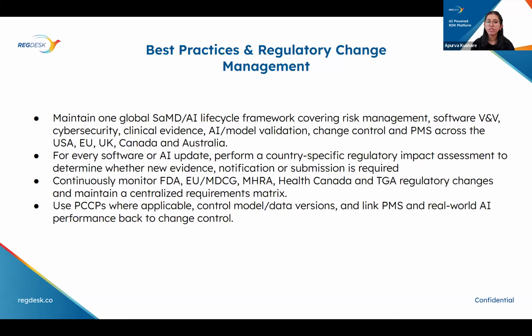Also, the manufacturers should continuously monitor FDA, EU, MDCG, also Health Canada and TGA regulatory changes, and also maintain a centralized requirement matrix. It is also important to take into consideration the local requirements, especially the medical device definition. Some countries, as I talked about, have some specific requirements on intended purpose. So it is important to read through the current guidance document that has been published by the health agency, and also the use of PCCPs where applicable, the control model or data versions, and also the link to PMS and real world AI performance back to the change control is also helpful for the manufacturers to get that feedback loop.